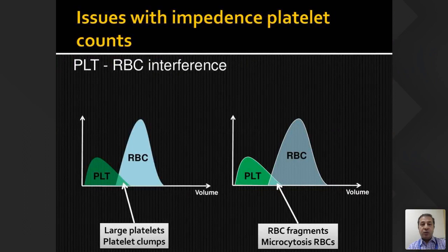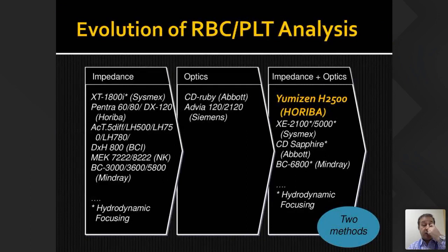Platelets and RBCs are counted in the same RBC-platelet channel, so there will be overlap between RBCs and platelets whenever there are smaller RBCs or larger platelets — that's when counts become relatively unreliable. This is where the importance of new analyzers comes into the picture. There has been evolution from impedance to inclusion of optics, and eventually combination of impedance and optics in some analyzers, giving dual platform methodology for the best possible platelet count.